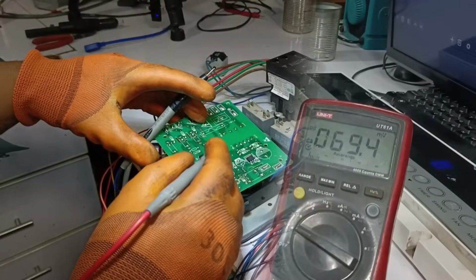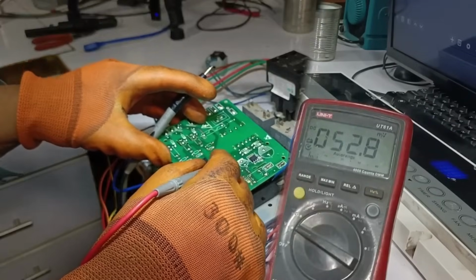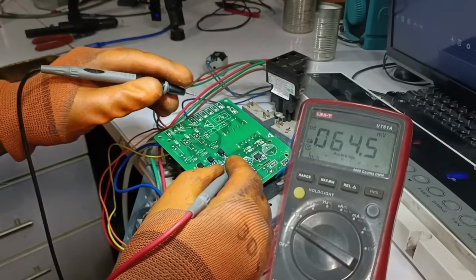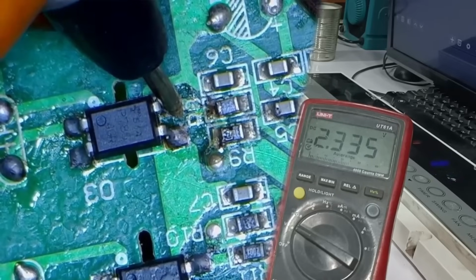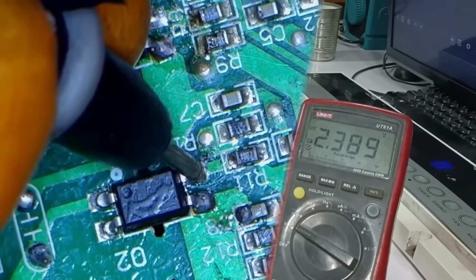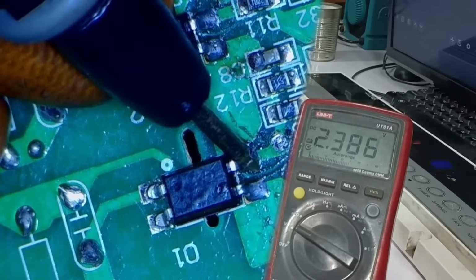We'll test the output of all 3 optocouplers. Using the positive probe on the capacitor's positive side and checking the optocoupler outputs with the negative probe, we see 2.3 volts on the first one, the same on the second, and 2.38 volts on the third. This confirms that all optocoupler outputs are functioning properly. The only issue remaining is the missing 120-degree phase shift. Everything else in the circuit is working correctly. The final check is to confirm whether the green status LED turns on. If it does, the system will operate normally.